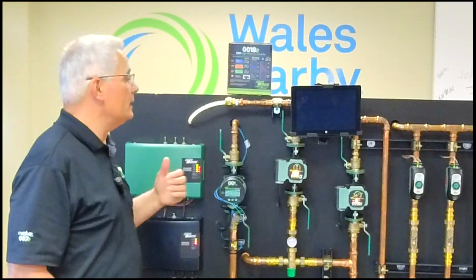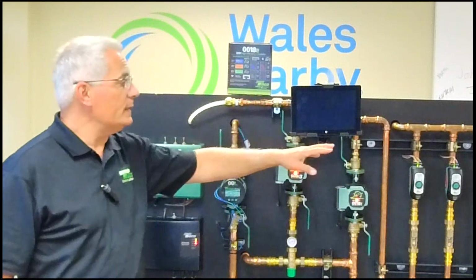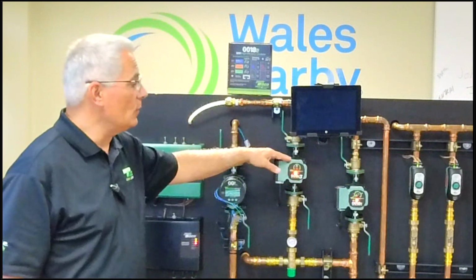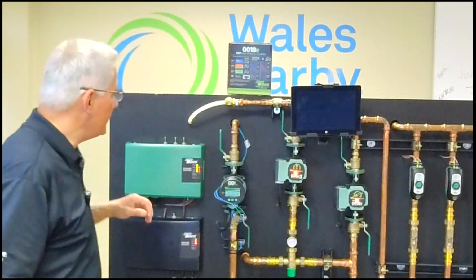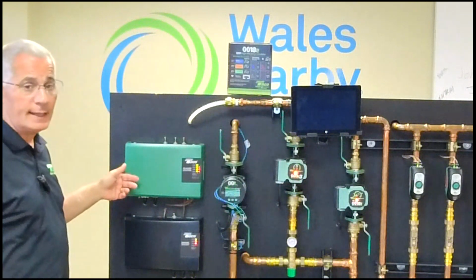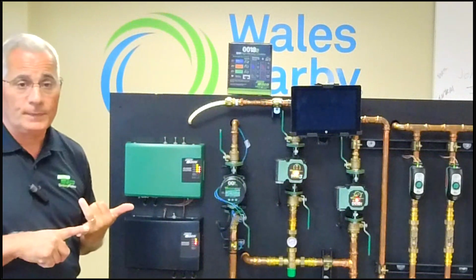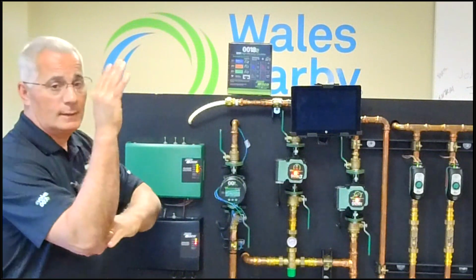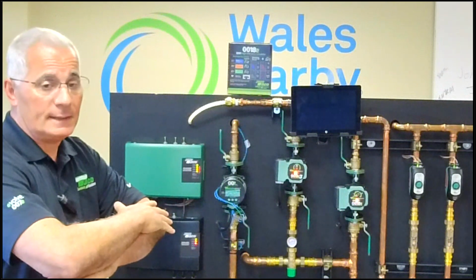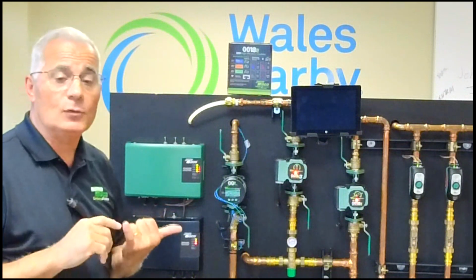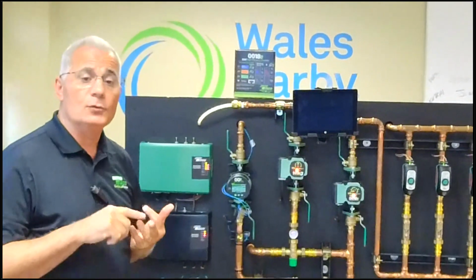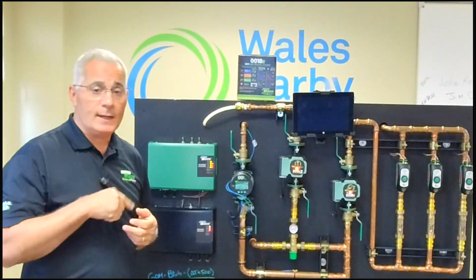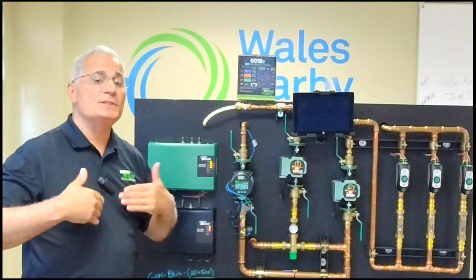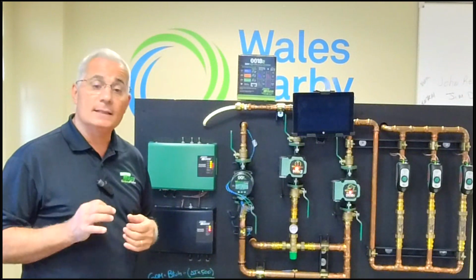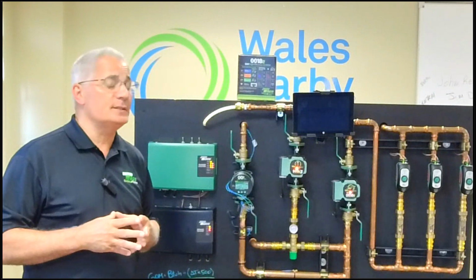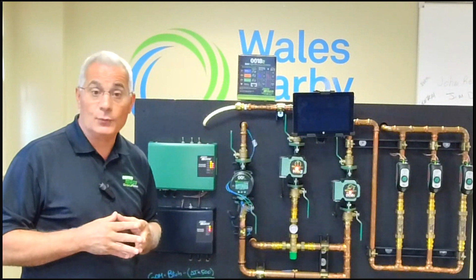Well, okay, because this zone may call when these zones are calling, or this zone may call when these zones are not calling. On my ZVC panel, on my dry contacts, I've got a main pump end switch that is set as a normally open switch that will close anytime anything on the panel calls. Then I have a normally open, a common, and a normally closed. So if I brought power to common, normally closed switch stays closed at all times unless I enable the domestic hot water priority.